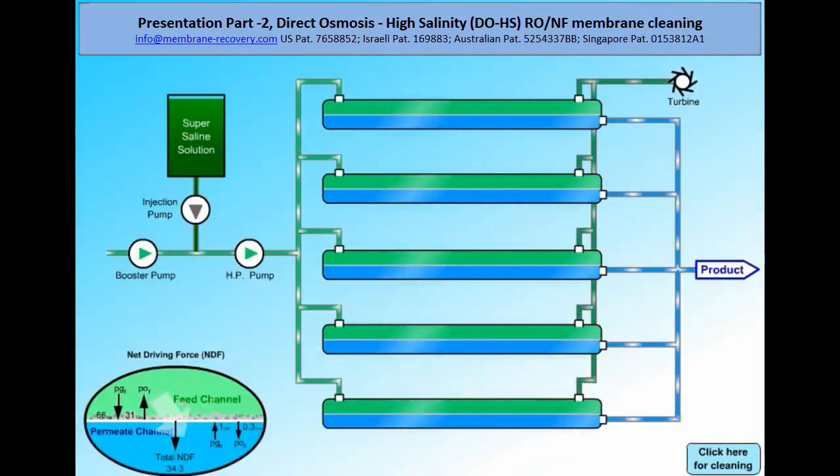Hi, in this second presentation, we'll see the real time that the direct osmosis cleaning requires. This backwash of RO and NF membranes can be done every morning for one minute without stopping the high-pressure pump, sort of like brushing your teeth.